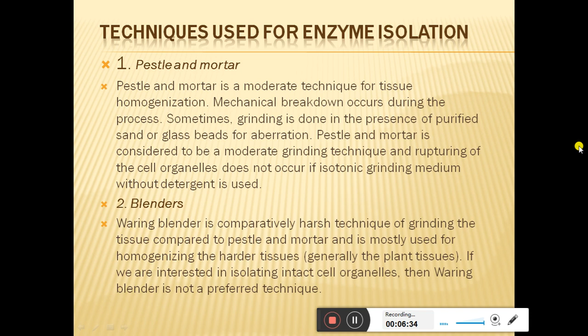The Waring blender is first operated at low speed for a few seconds and then at a medium speed for a few seconds before bringing it to a high speed. The time of grinding at various speeds is decided according to the nature of the tissue being ground. If it is a soft tissue, the time needed will be very less, and if it is a harsh or hard tissue, more time is needed for the grinding.